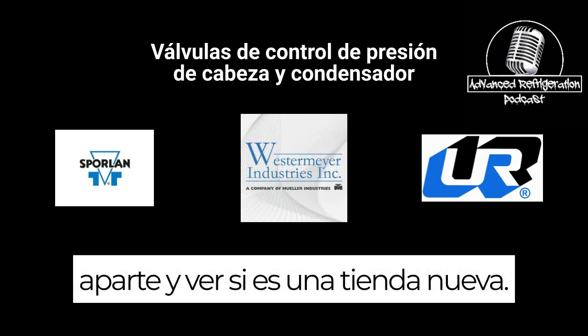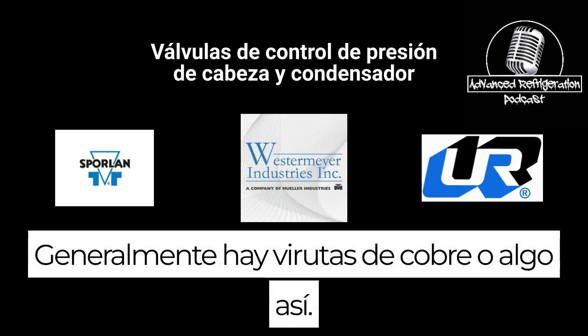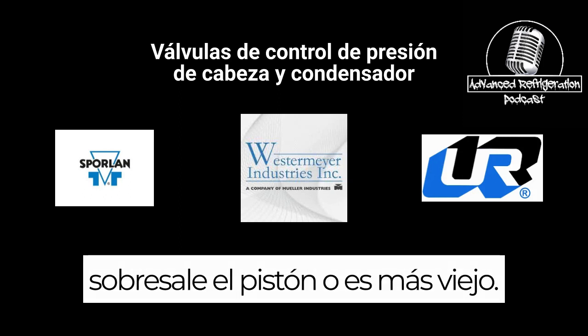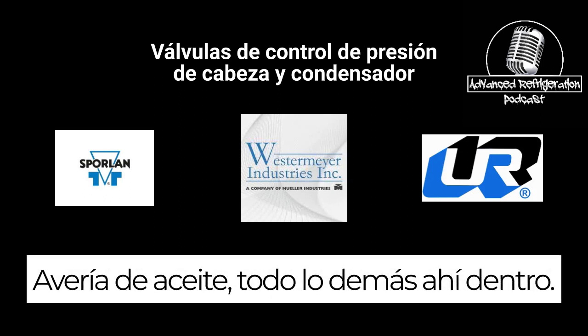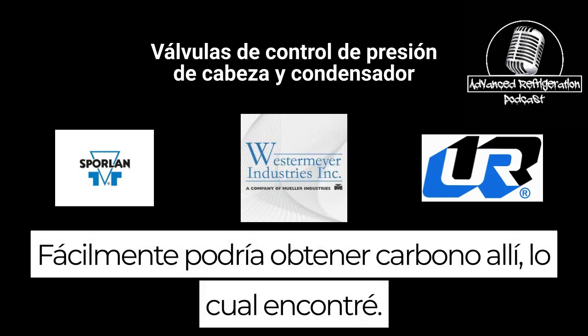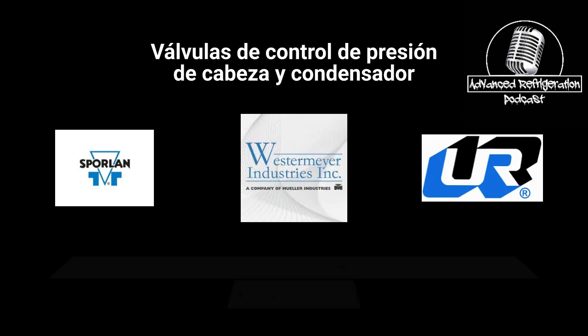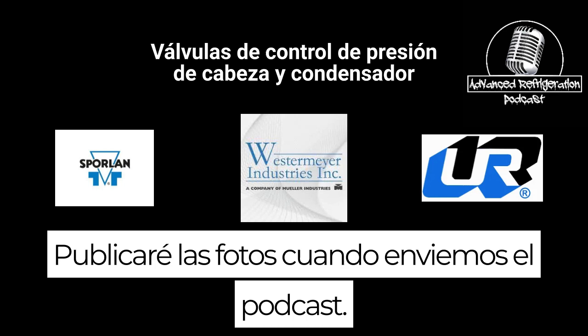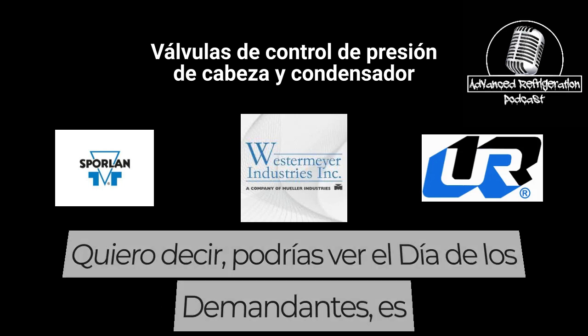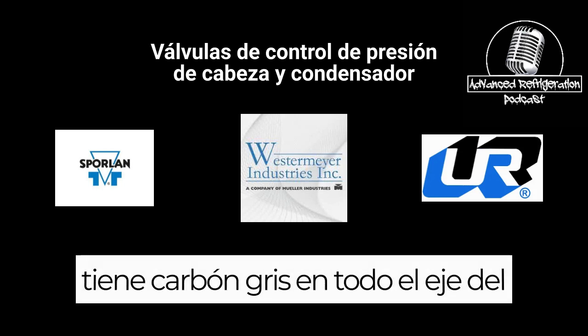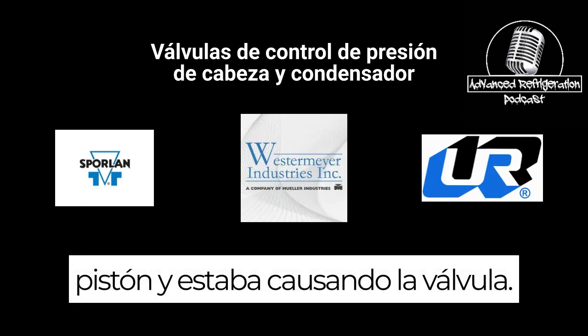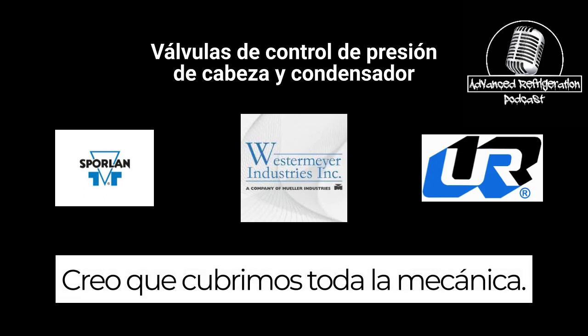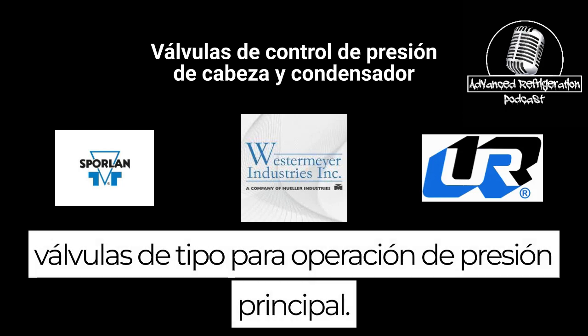If it's a brand new store, generally there's copper shavings or something in it sticking up the piston. Or if it's older, oil breakdown, everything else inside there. You could easily get carbon on there, which I found. I'll post the pictures when we send the podcast out of the one that I pulled apart. You could see plain as day, it's got gray carbon all over the shaft of the piston, and that's causing the valve to stick.